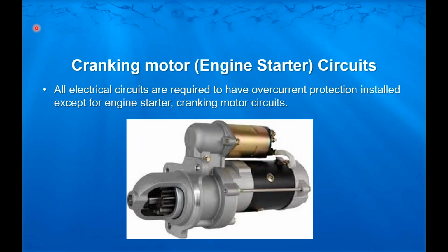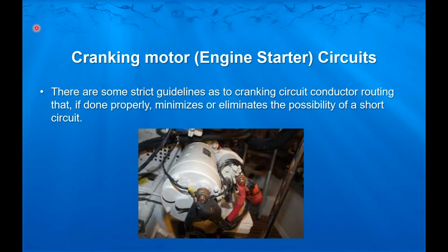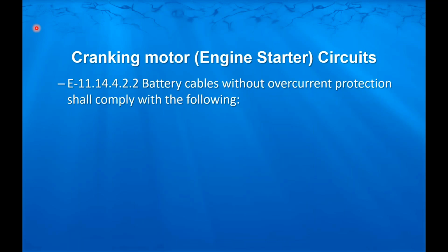There is one exception. All electrical circuits are required to have overcurrent protection installed except for engine starter cranking motor circuits. They do not need overcurrent protection. There are some strict guidelines as to these circuits that, if done properly, will minimize or eliminate the possibility of a short circuit. They're there to eliminate damage to that piece of wire because we're not putting overcurrent protection in. Well, the first thing that's got to be done, because we're not putting any overcurrent protection, it's got to be, again, in a sheath of some sort.